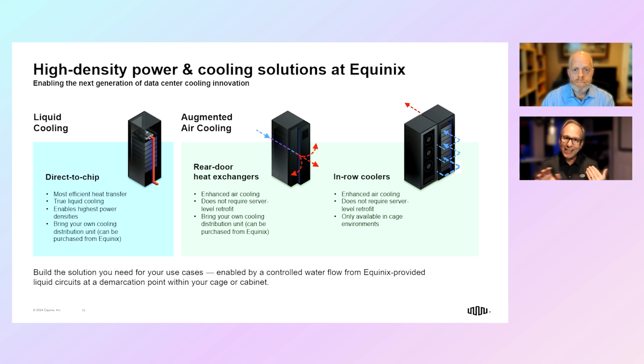Now, it's not exactly liquid cooling - we call it enhanced air cooling, since the server chips are still cooled by air. But this method does bring liquid closer to the rack, making the air cooling much more effective. Similarly, in-row coolers enhance air cooling by bringing liquid closer to the heat-producing processors. These coolers are placed right next to your infrastructure, blowing colder air into the cold aisles and directly onto your hardware.